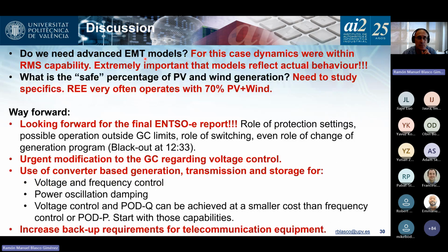Do we need advanced EMT models? For this case, you see that the dynamics were within the RMS capability. But what was important is that the TSOs stated that some generators didn't behave as they expected. So this is particularly important. Models should reflect the actual behavior. That's very, very important, because otherwise decisions taken on models that do not reflect the actual behavior can be problematic.